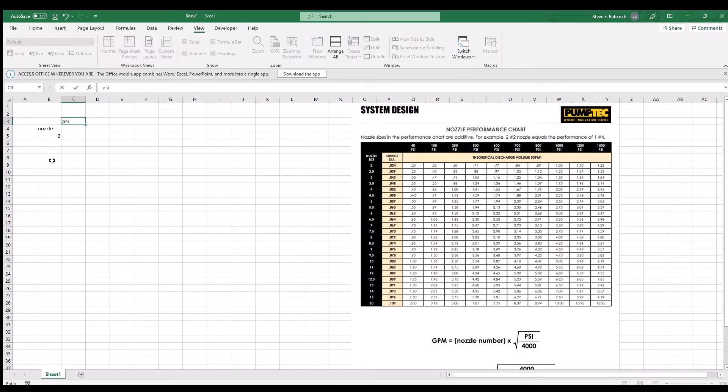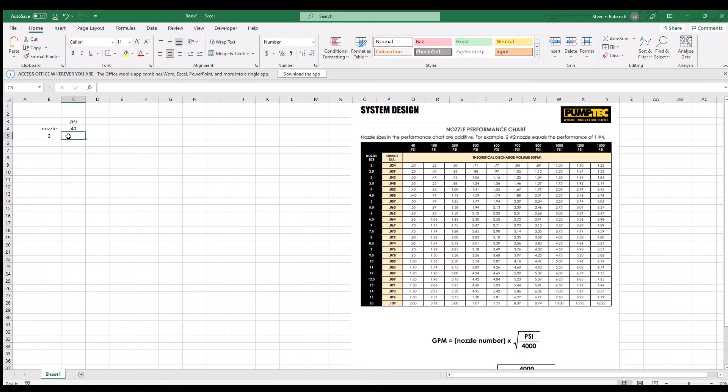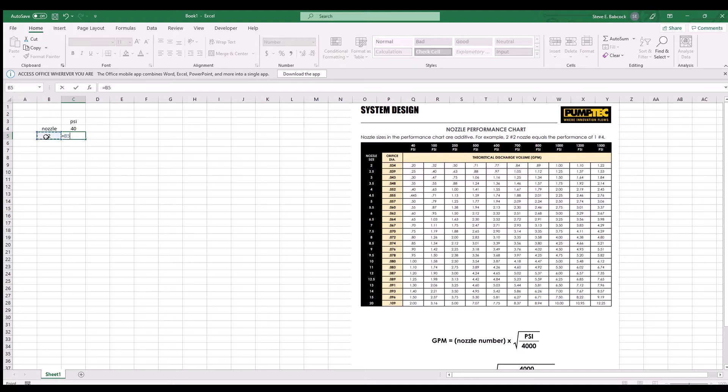Now we're going to calculate the GPM in cell C5 by typing the formula below the chart. GPM equals nozzle number times the square root of the pressure which is 40 over 4,000.